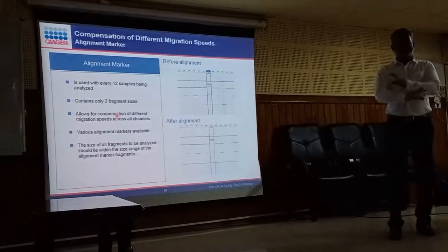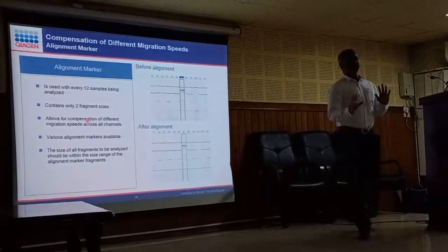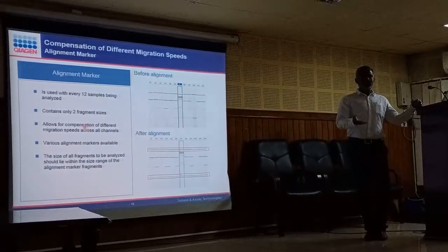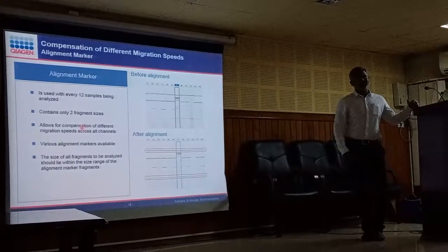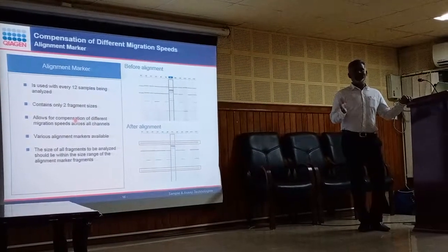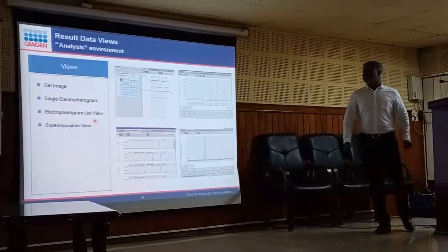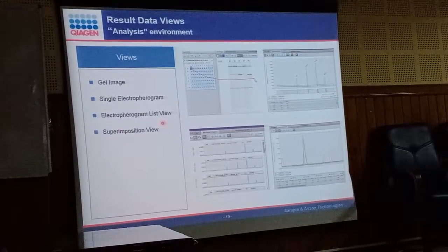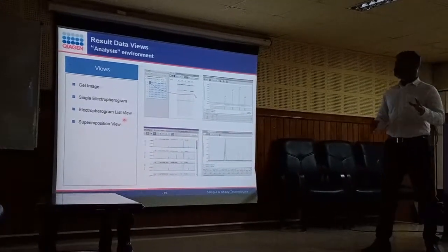Load your cartridge inside the machine, choose the right method, open the nitrogen cylinder, run the sample, and get your data — that's it. With minimum training, a BSc student with a technical background can handle the system within a week; MSc students should manage in one day or half a day. Training is two days: day one covers calibration, instrument handling, setting markers, and output; day two uses your own samples for thorough data analysis training.